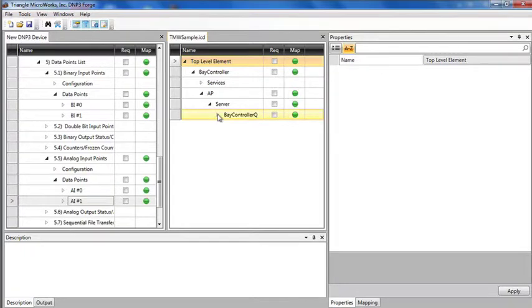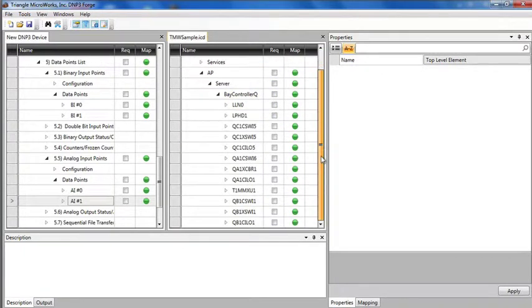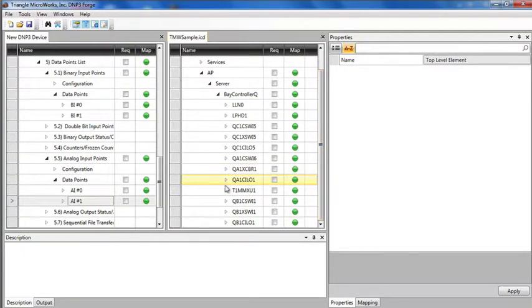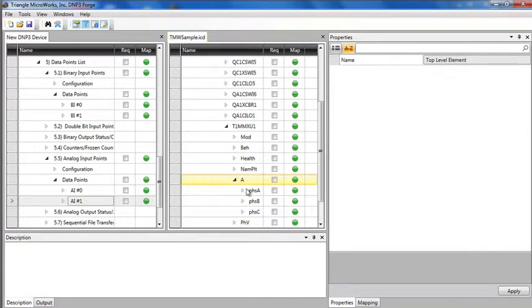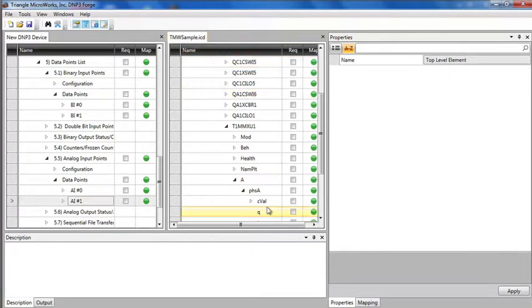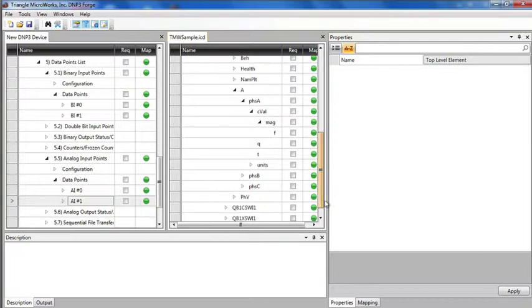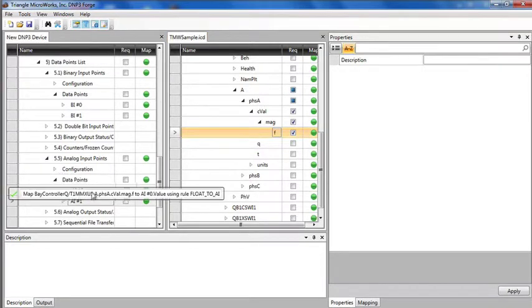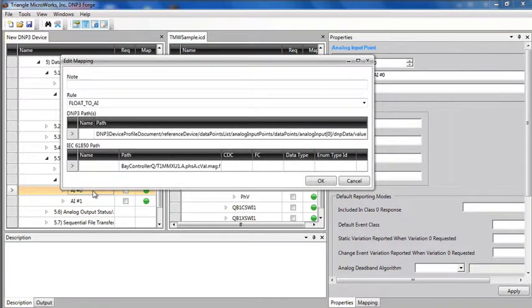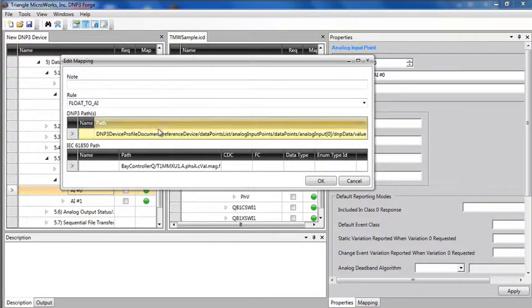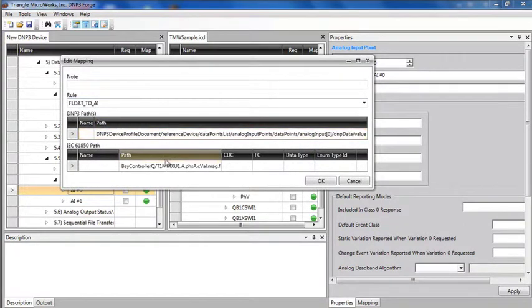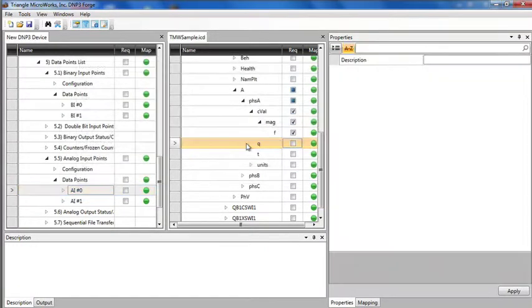Now I can expand down into my ICD file and find the point I want to map. For example, let's look at the phase A current. Since I am mapping this point, I want it to be required. So I will click this checkbox, and then I can just drag the point and drop it on my analog value. Edit mapping dialog pops up and lets me verify the mapping and shows me what rule is being used.